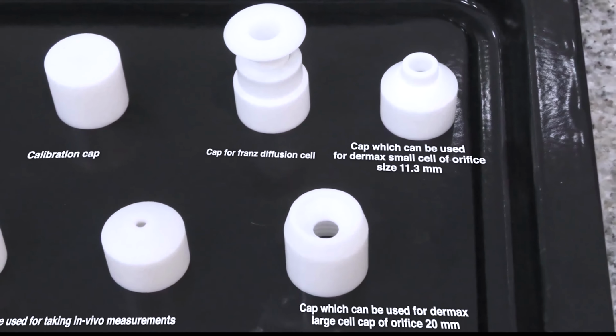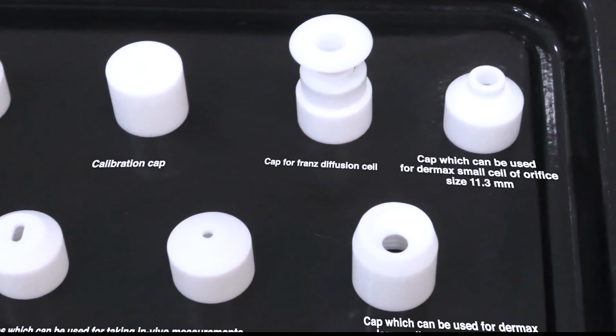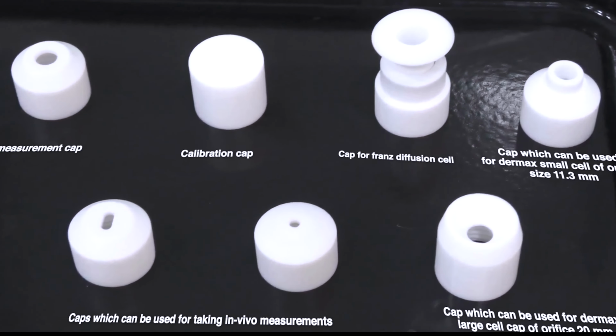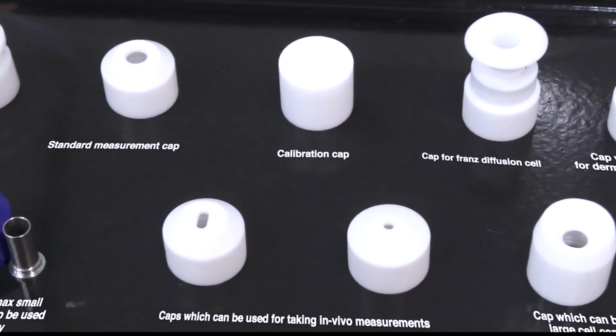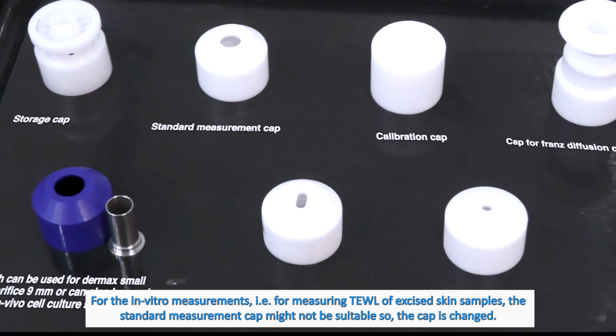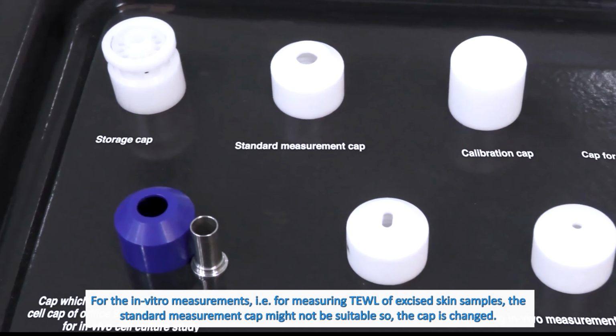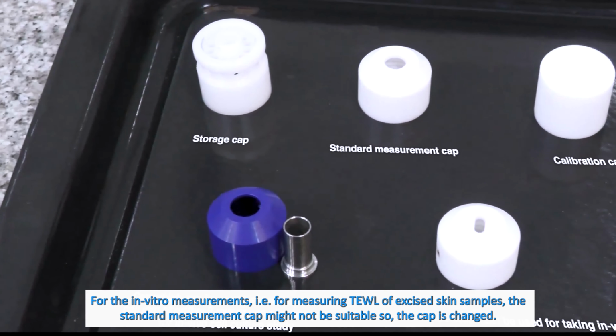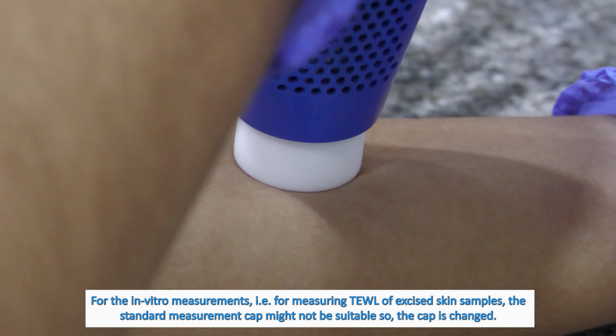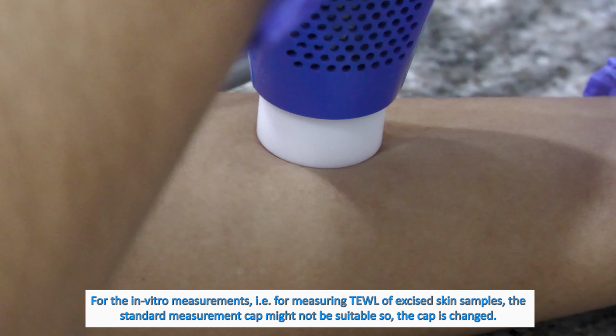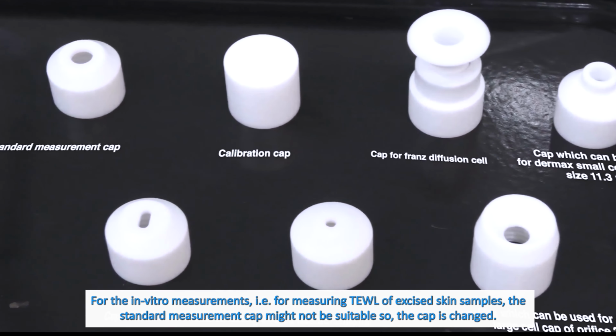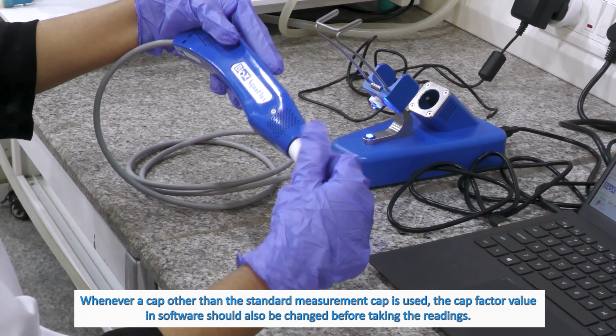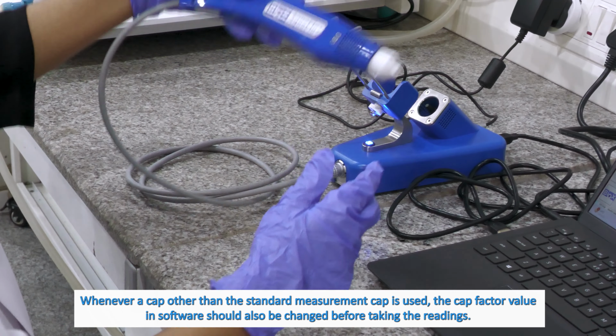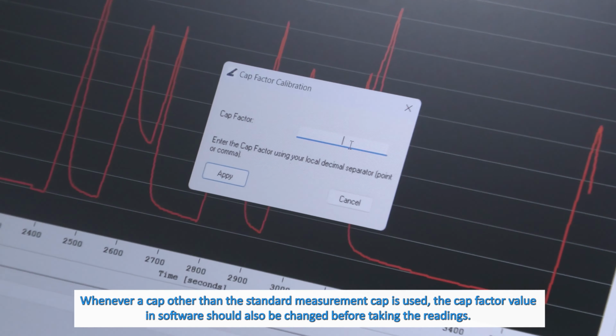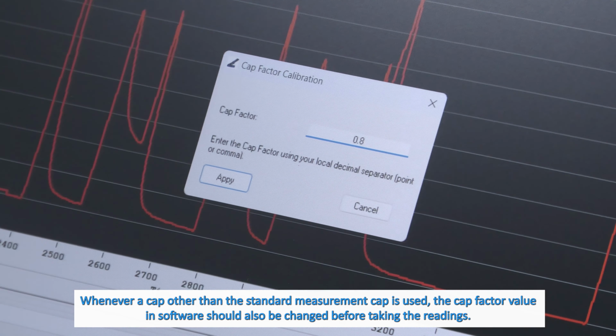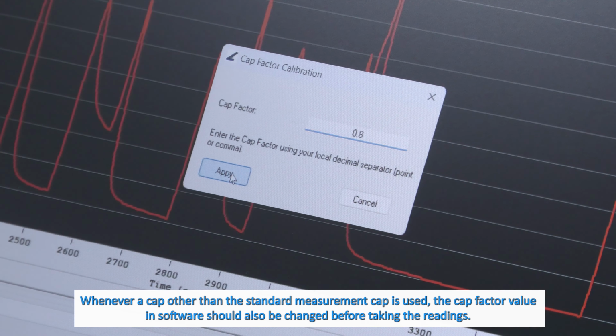There are different caps available for different applications. Here in this video we'll show two examples of caps and adapter. For the in vitro measurements, i.e., for measuring TEWL of excised skin samples, the standard measurement cap might not be suitable, so the cap is changed. Whenever a cap other than the standard measurement cap is used, the cap factor value in the software should also be changed before taking the readings.